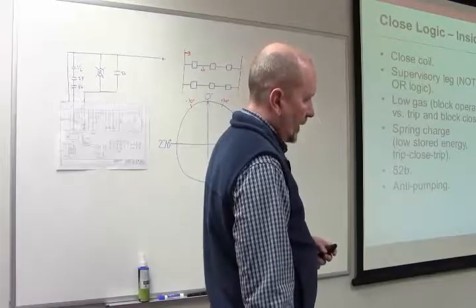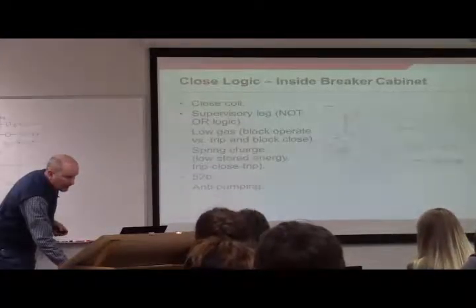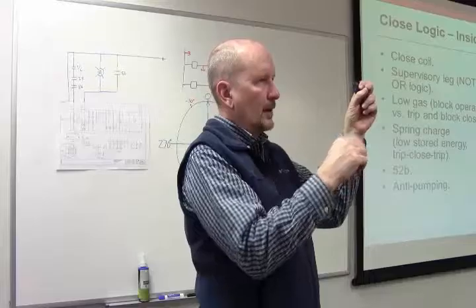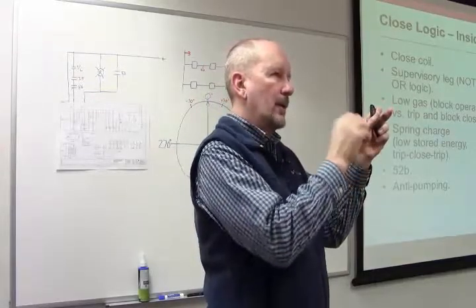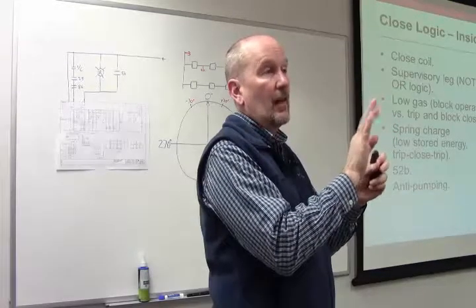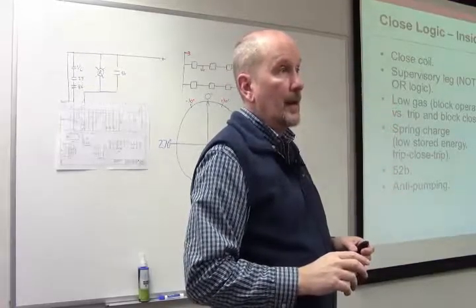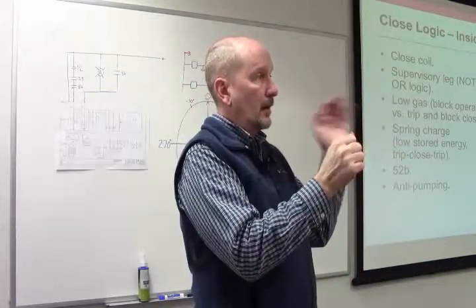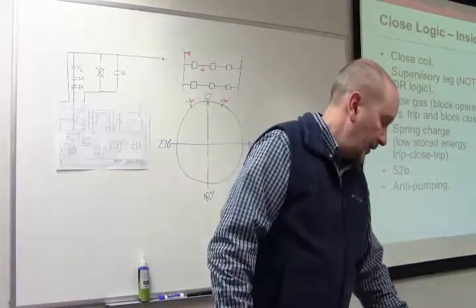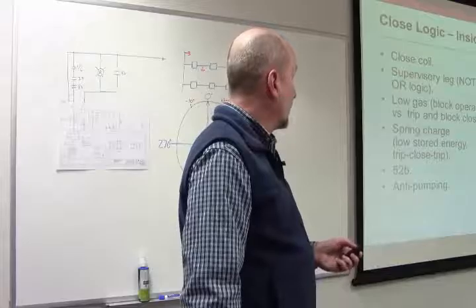And then we talked last week about the anti-pumping scheme. It's located right over here. When you close the breaker but you still have DC applied to that circuit, it's going to prevent that from going to the closed coil and stay locked in until you remove DC from that circuit. It'll prevent you, if you have a standing close and a standing trip from closed trip, closed trip, closed trip on the circuit breaker. Besides wreaking havoc on the electrical system, it's also going to damage the breaker.